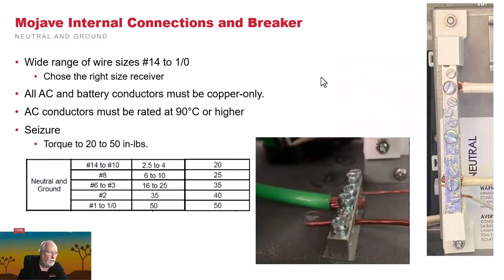When you look at the ground, it's super easy to hook up to. We provide a bus in the bottom of the Mojave chassis. You'll see a large green wire here. There could also be a secondary large green wire. The one would be from the battery compartment. There'd be another one from your panel, and another one going to the other panel, if that's the way you routed your grounds. All conductors again must be copper. The size ranges are 14 gauge to 1/0 gauge, and all of the conductor torque settings are set right there based on its size. This is right out of the manual. So they can enter from either side, and again, remember, they're different torques. The screws are designed to be either flathead, XZN drive, or Robertson drive.